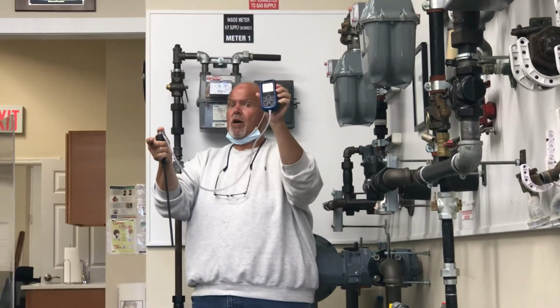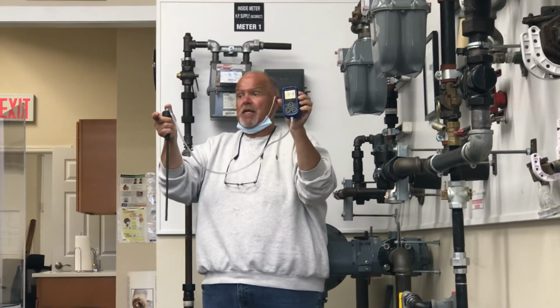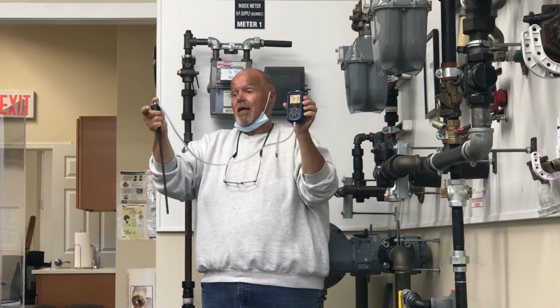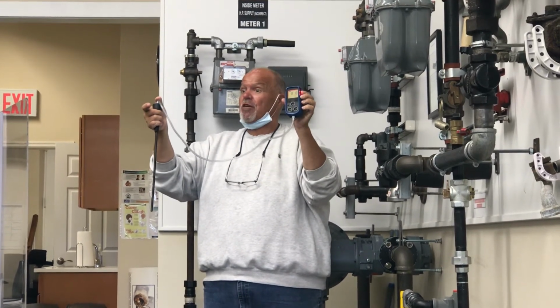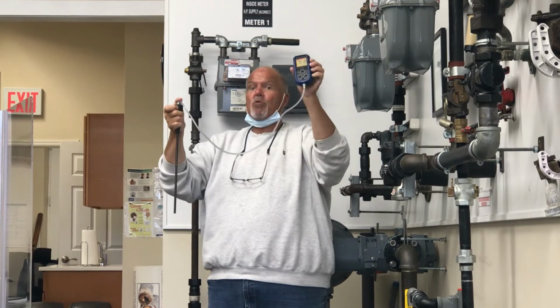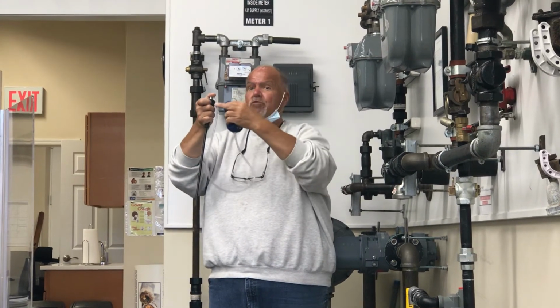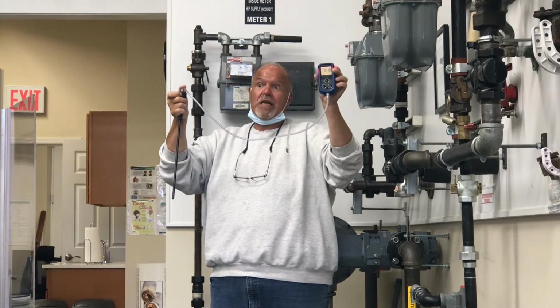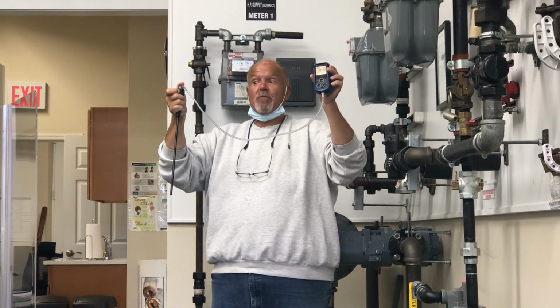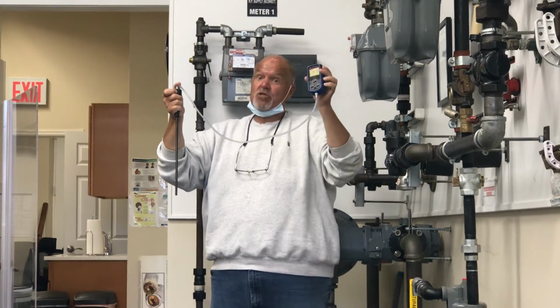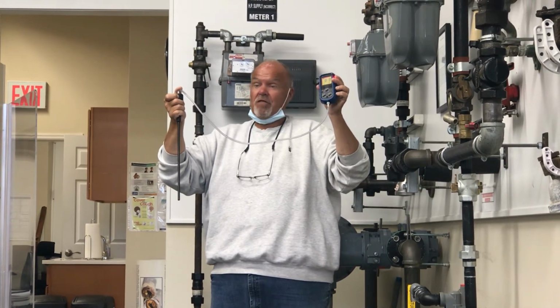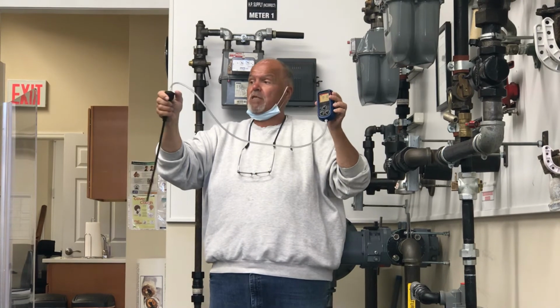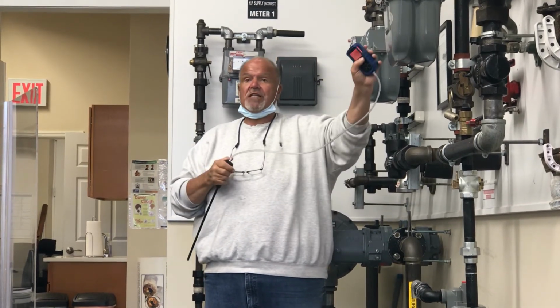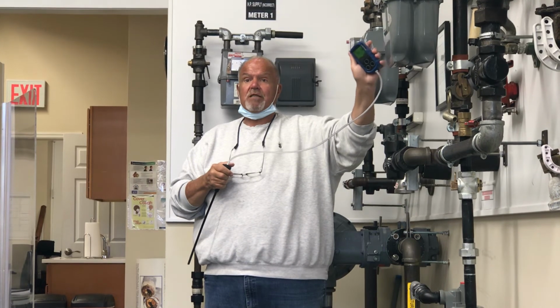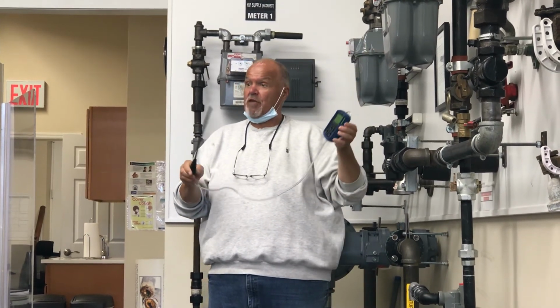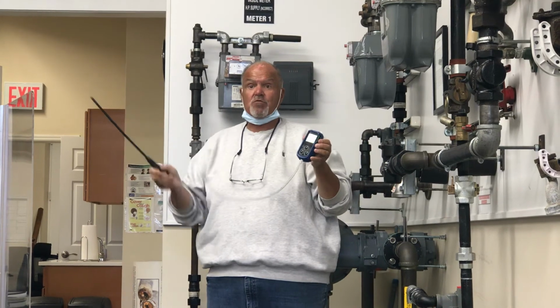The machine should alarm, saying, I can't suck anything in, something's wrong, which is the desired result. You've created a block, and you want to make sure the machine is reacting to that. That proves that you have no leak in the tubing. You've created a vacuum. If there was a leak in the tubing, it will not alarm. Then you have to replace the tubing or replace the device itself. So clear the block, release the block, hold the blue button down until the pump comes on. Now you can proceed with your leak survey as we demonstrated earlier during today's prior discussions.